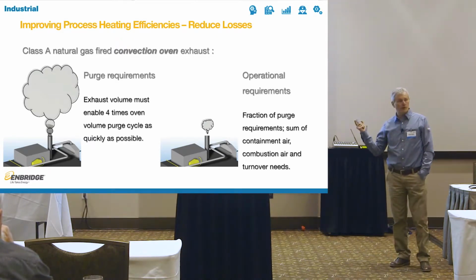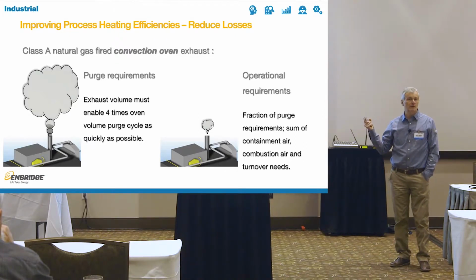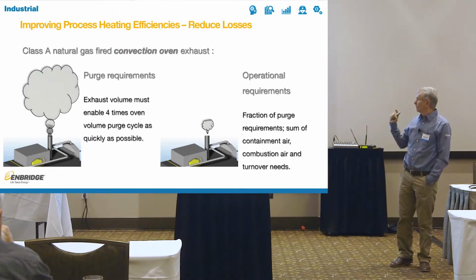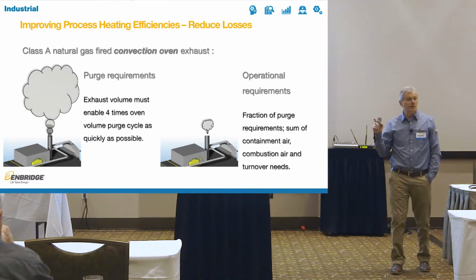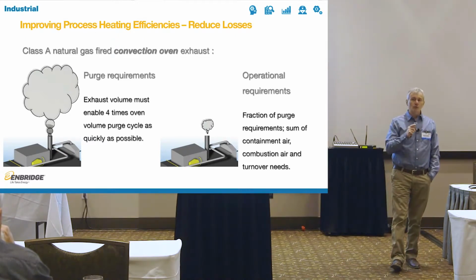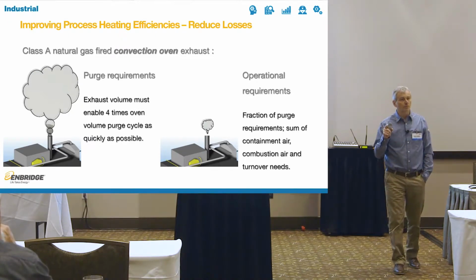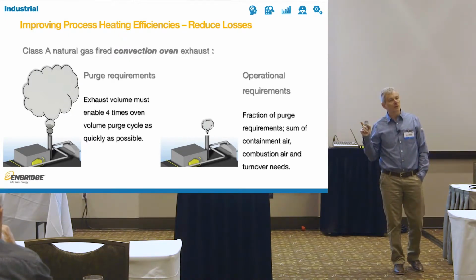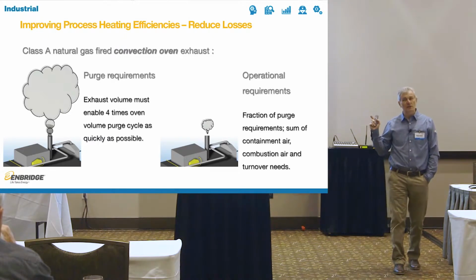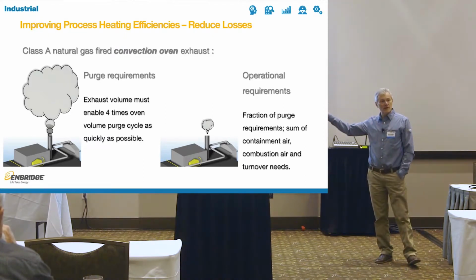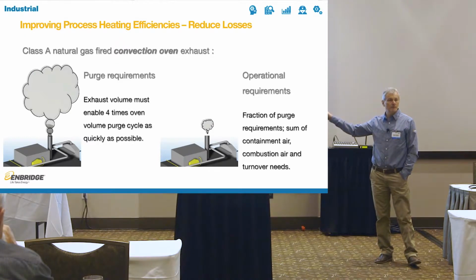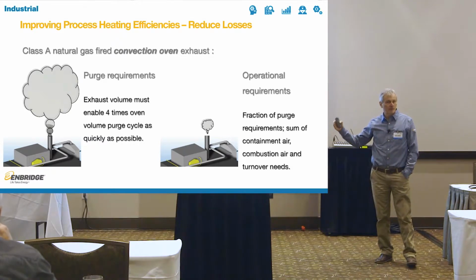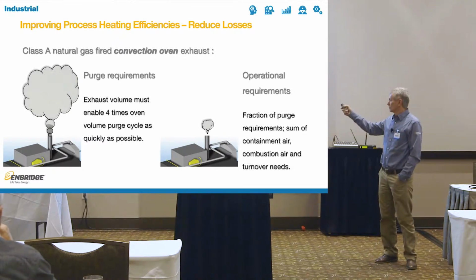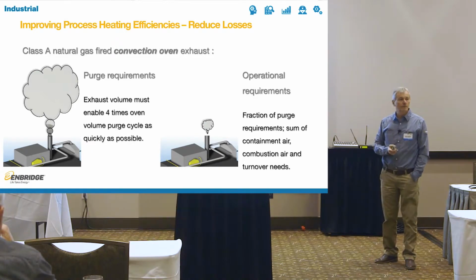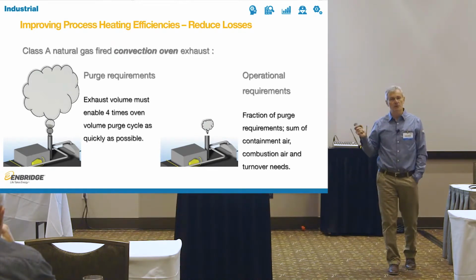All of our ovens, or most of our ovens, are fairly old, 20 years, 25 years, 40 years, not uncommon. At that time, there were no VFDs. And none of you would be willing to wait on your process to purge every time you have to restart it for 2 or 3 hours. So the exhaust fan was sized to minimize the purge requirement to about 10 to 20 minutes. You want it purged quickly. VFDs were not very common then, so you were running that exhaust all along. You don't need it, but you were running it because that was the only way to do it.